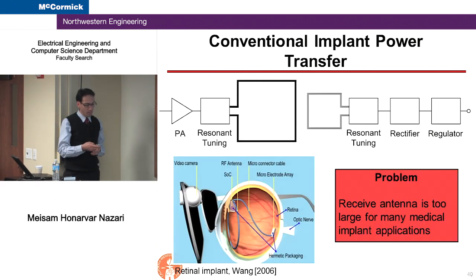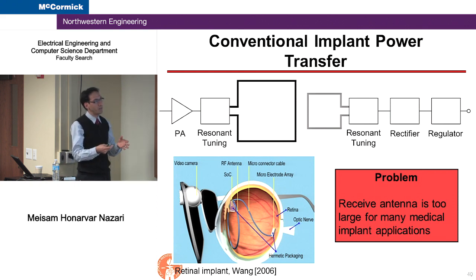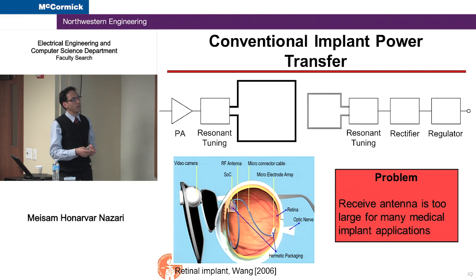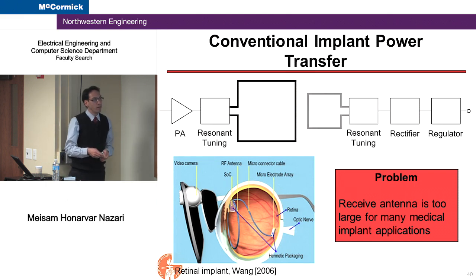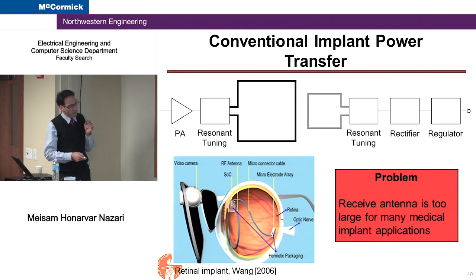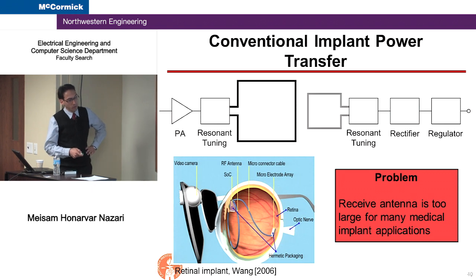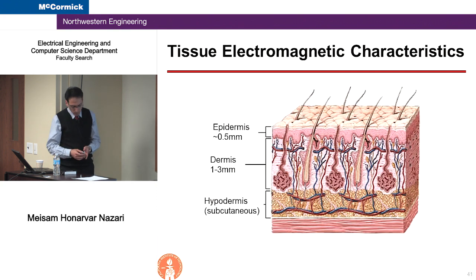As I mentioned, one way of powering the device is to use batteries, but batteries are bulky, so we can use RF powering from outside. Currently available RF powering devices are used for implantable systems or for retinal implants. They use large coils and low frequency in order to minimize tissue loss. But for an implantable glucose monitoring system, we cannot use very large coils and antennas. So we have to find a different frequency band to do that.